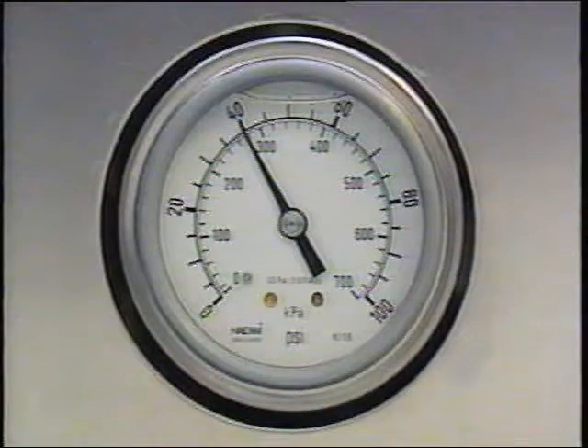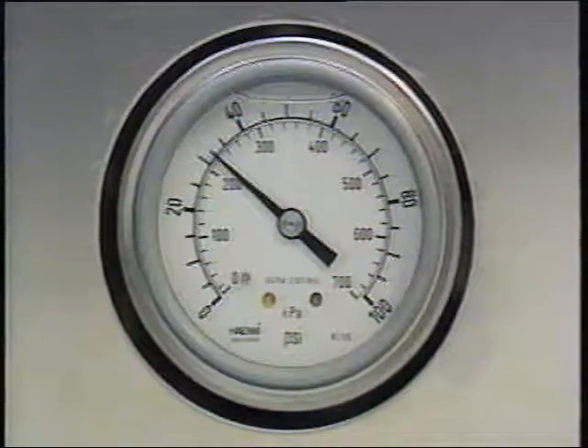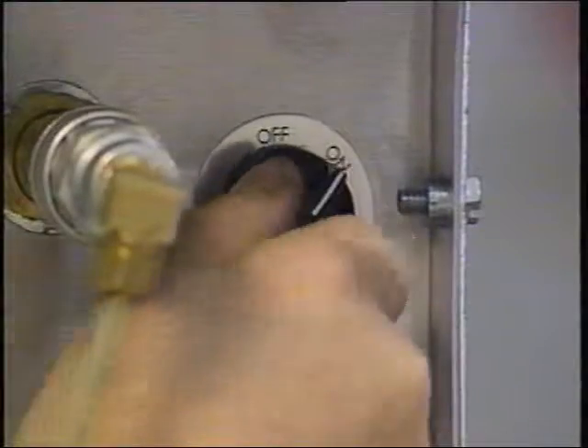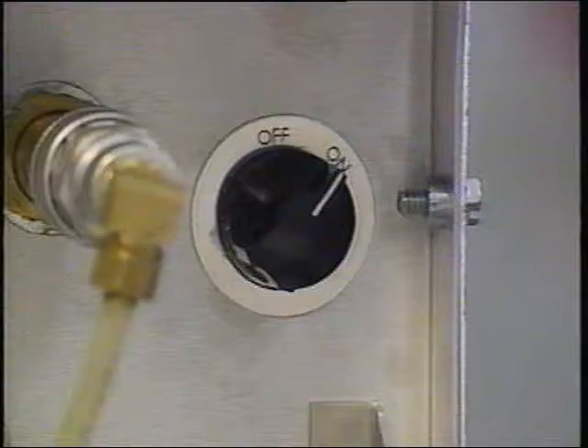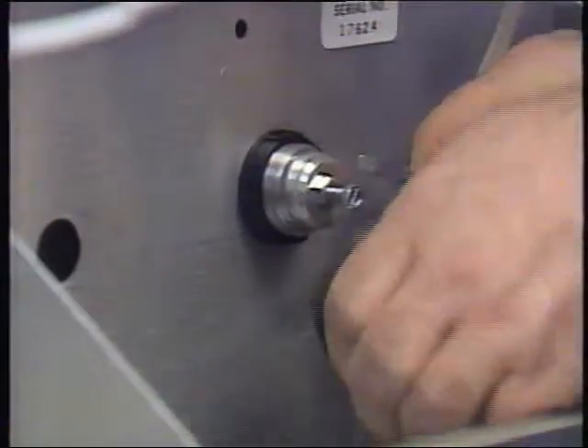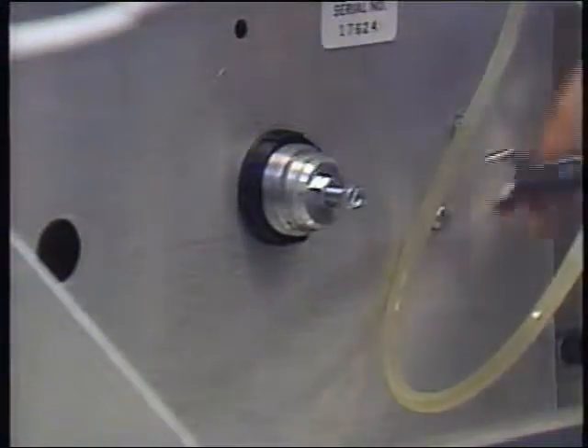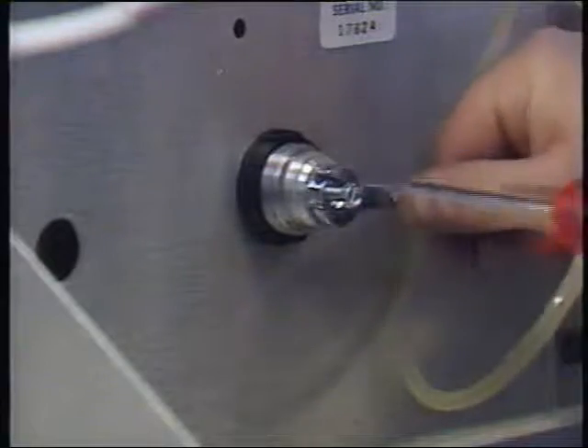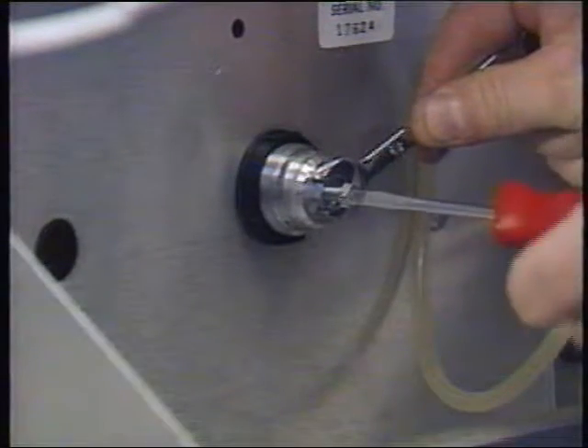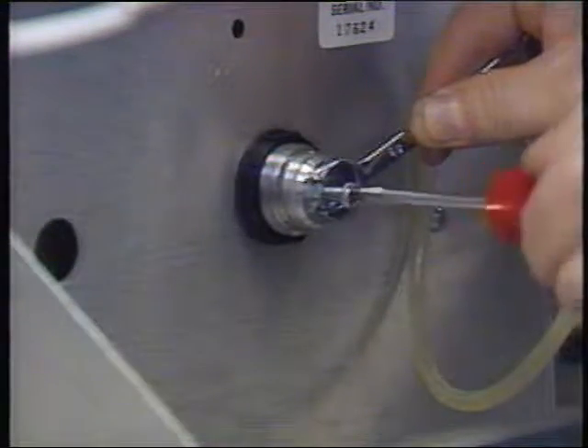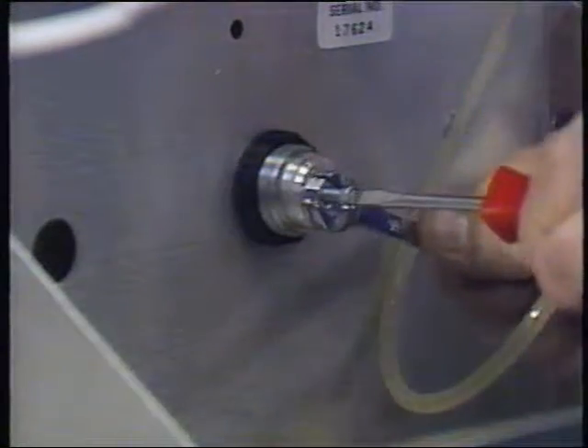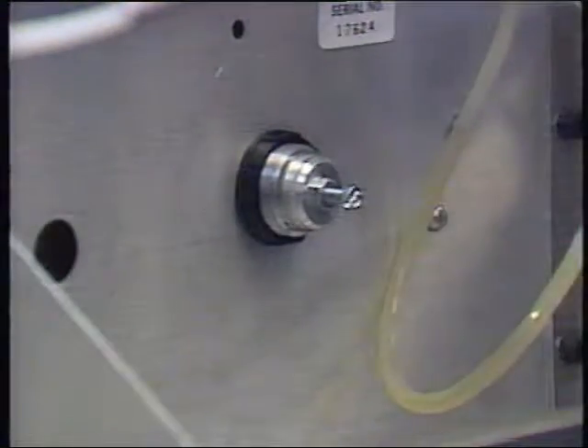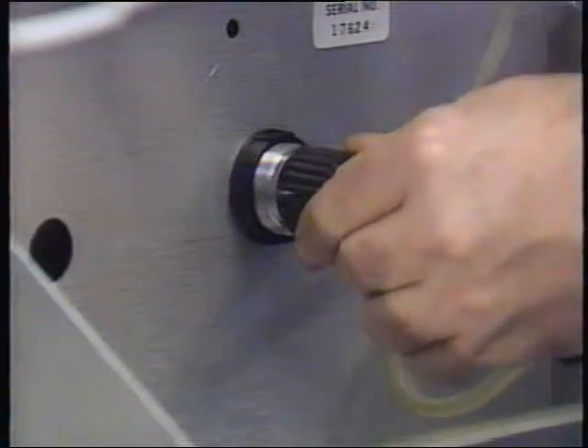The fuel pressure is set at the factory, but it may need to be adjusted. To adjust the fuel pressure, turn the shutoff valve to the open or on position. Then remove the black regulator cap and back off the lock nut. Turn the screw until you get the proper setting. Retighten the lock nut, replace the cap, and turn the unit off.